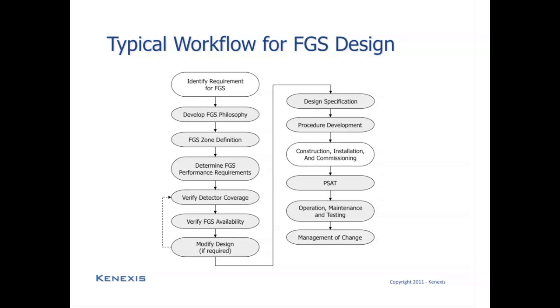After the performance targets have been achieved, the next step is to specify the design of the fire and gas system that has had its coverage and availability defined. And this is akin to the safety requirement specifications for a traditional safety instrumented system. As a matter of fact, many people will refer to these specifications as the FGS safety requirement specifications. This is typically going to include things like detector placement drawings, cause and effect diagrams for the actions that are taken by the fire and gas system, and also general requirements on the attributes for performance of the fire and gas system.